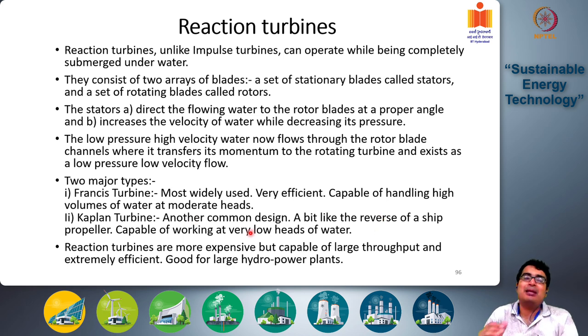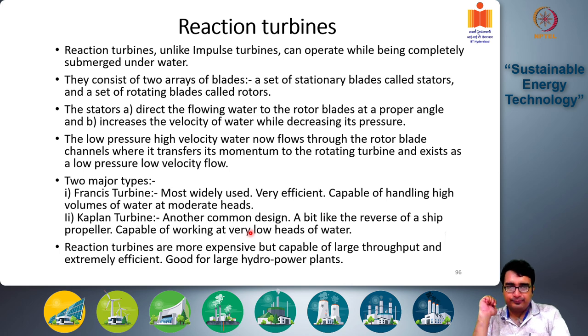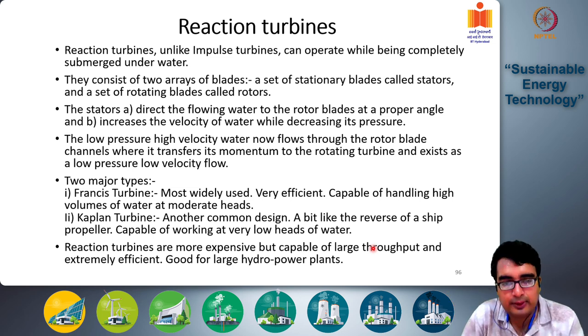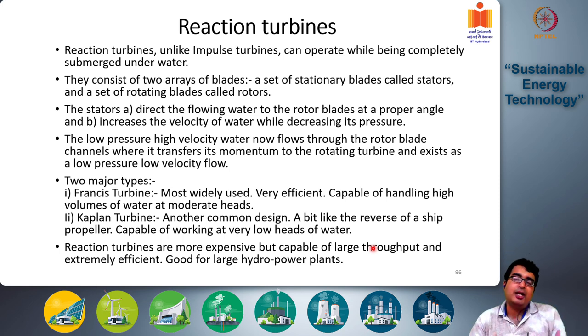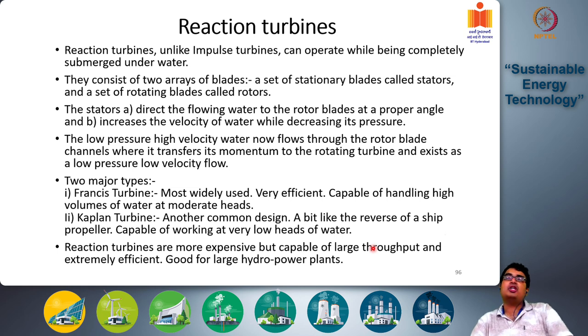The advantage of the Kaplan turbine is that it is capable of working at very low heads of water. If you have a river where the inclination is very slight, the water head is quite low, but there is a large volume of flow, the Kaplan turbine is ideal for such conditions. Reaction turbines are more expensive in general, but they are capable of handling large throughput and are extremely efficient, with very small frictional losses compared to Pelton turbines, making them best suited for large hydropower plants.